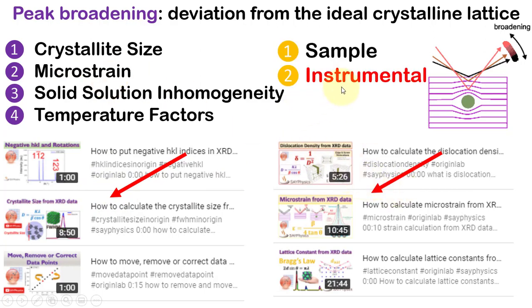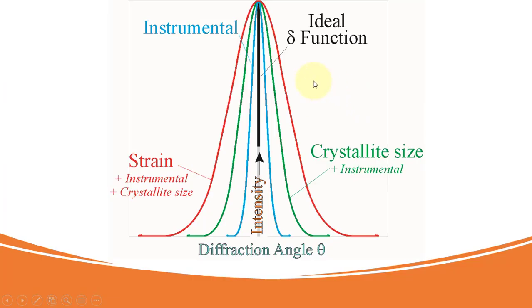However, broadening of the XRD peak is not only due to the sample but can also be due to the instrument. To get the actual broadening due to the sample, we will have to subtract the broadening caused by the instrument, which can be done with the help of measurement of some standards. Here we can see the magnitudes of contribution to the peak broadening from the instrument as well as from the sample.